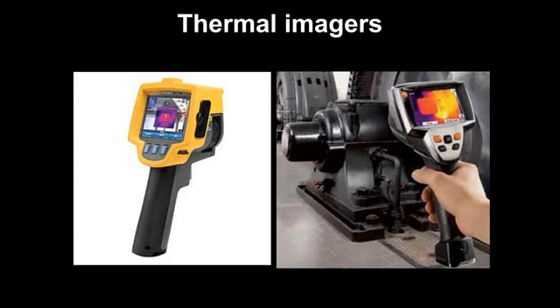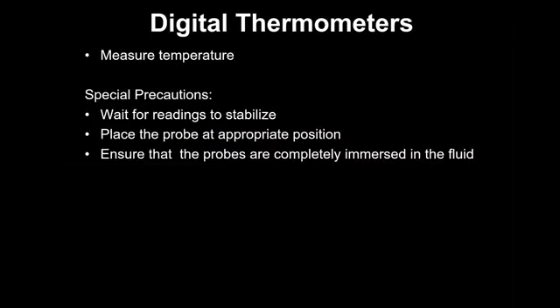We have even used it for a cooling tower, to study the distribution of water and the temperature profile of the water which is falling in the cooling tower. We have taken thermal imaging of that falling water and seen if the distribution is proper, cooling is proper or not.